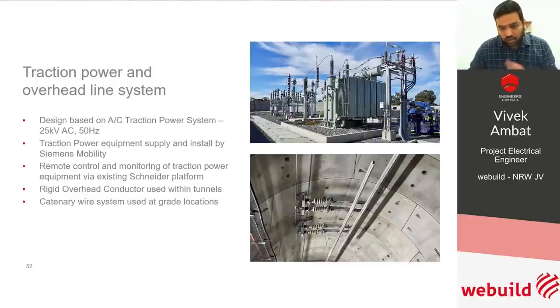Also, as mentioned before, inside the tunnel we've used a rigid overhead conductor system. As part of this project, we've introduced what's called a fixed earthing device into the PTS network - a system that isn't currently used in PTS's or the client's network. The fixed earthing device has been designed and implemented to provide a safe way of earthing the overhead lines when required, for emergency scenarios or maintenance work.